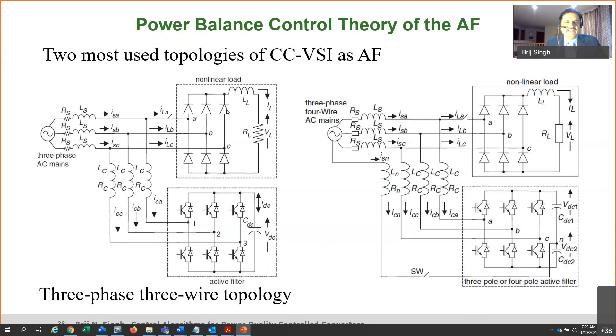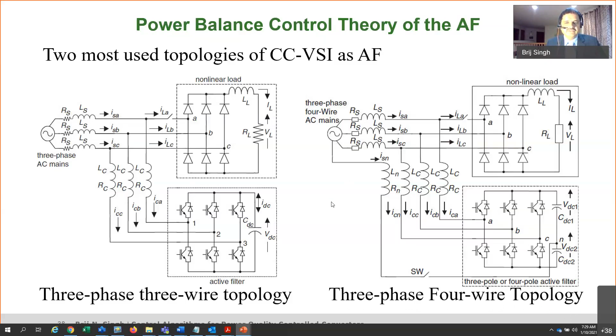The most used topology basically allows you to eliminate the third phase — we're talking about a 3-phase 3-wire or 4-wire system now. I'll skip a couple of slides due to time constraints. This is the 3-phase 3-wire system, and this is the 3-phase 4-wire system. The reason is that when you have an unbalanced load, oftentimes the neutral has a lot of current, so you want to compensate for that. That's why 3-phase 4-wire systems are very commonly used in hardware.